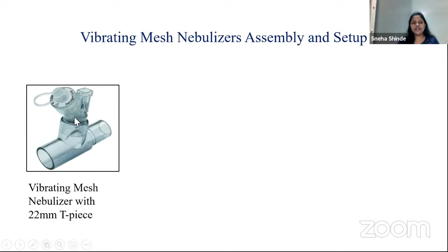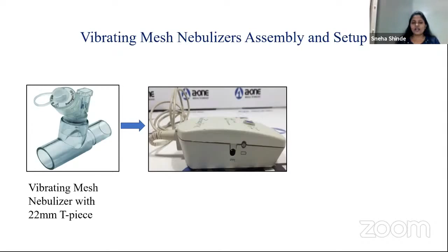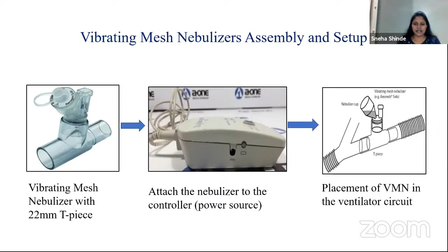Then we have to attach a controller to the nebulizer over here. The controller powers the nebulizer. Vibrating mesh nebulizers do not need any external oxygen or air supply. They are powered by the controllers. Then this nebulizer will go into the ventilator circuit wherever desired, after the Y-piece or before the Y-piece, in the inspiratory limb, 15 centimeters before the Y connector. So this is a typical setup for mesh nebulizers.